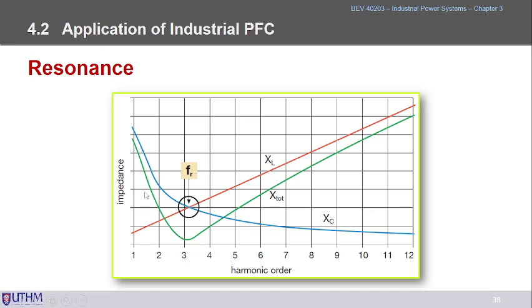So that means we need to have a so-called resonant filter to filter this out, and we divert it a little bit. When it is near the third order harmonic, but not exactly at the third order harmonic, it's quite okay, it's safe. But when this point is near to either the 3rd, 4th, or 5th or whatever, it will give you resonance.